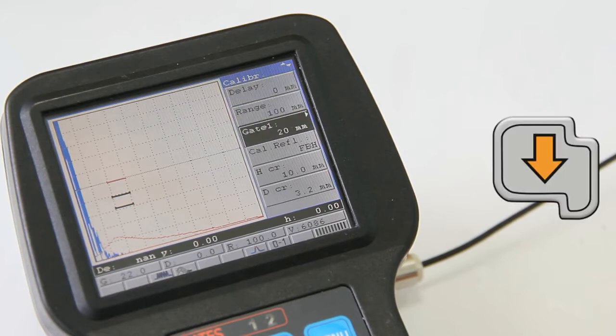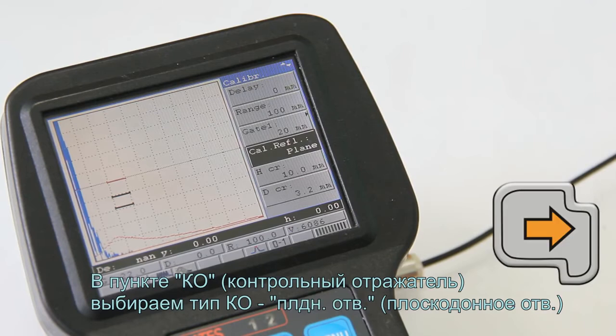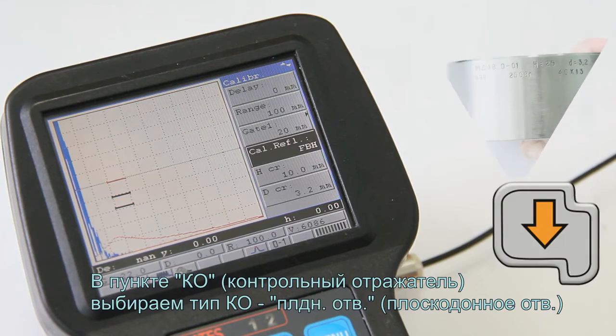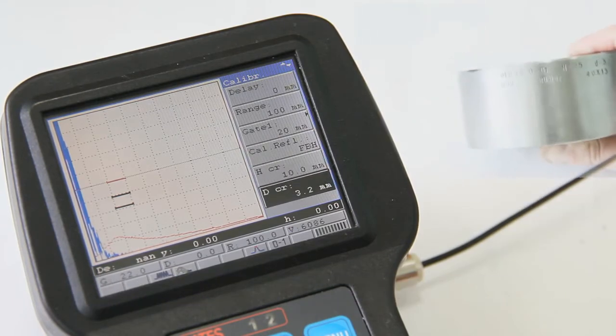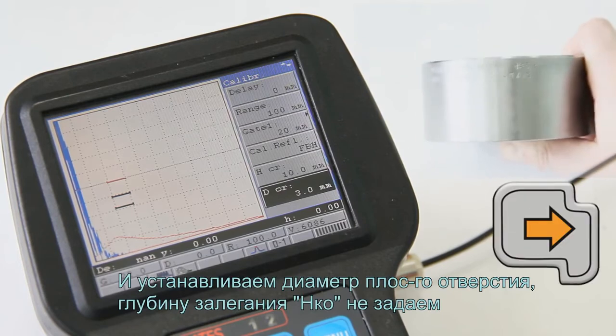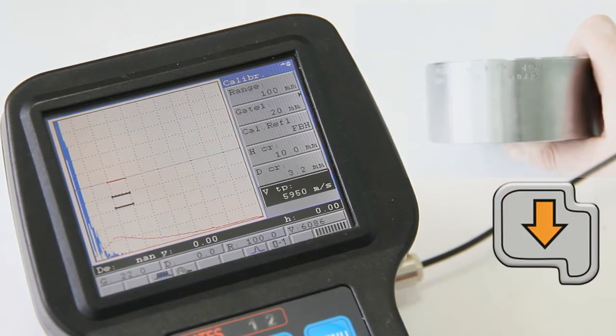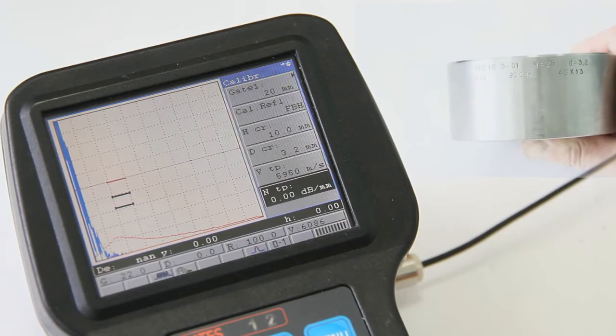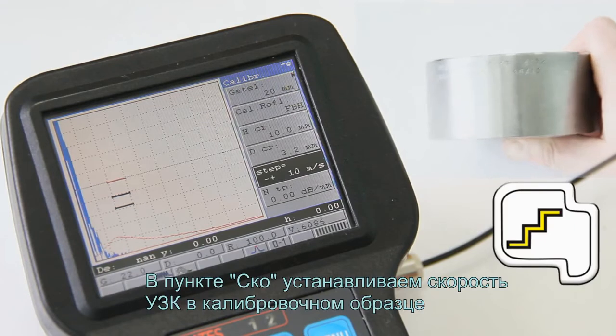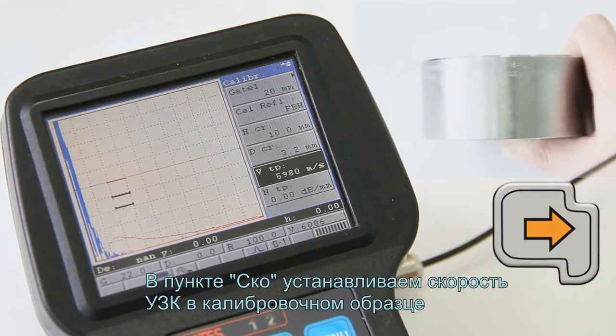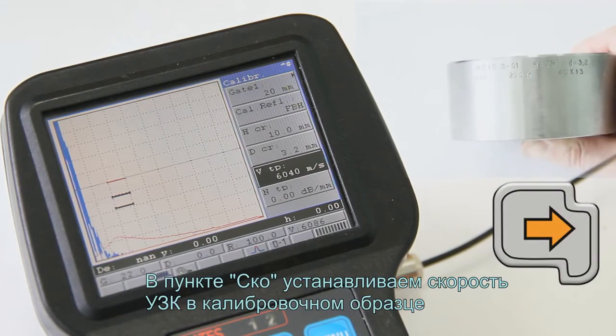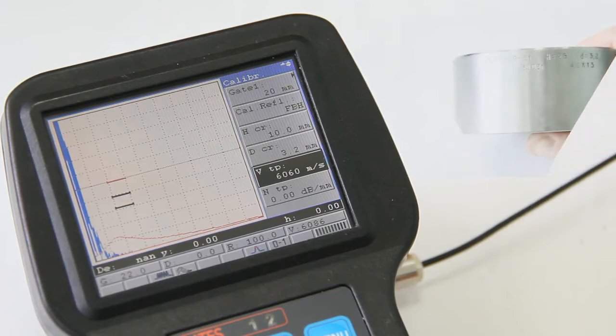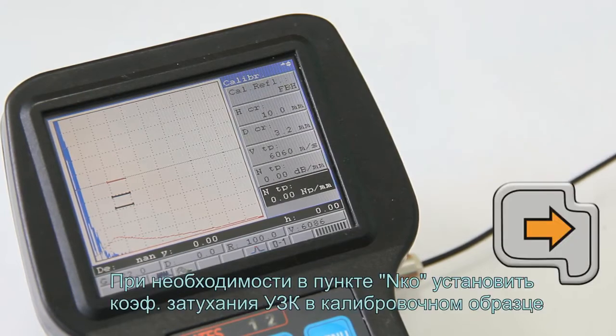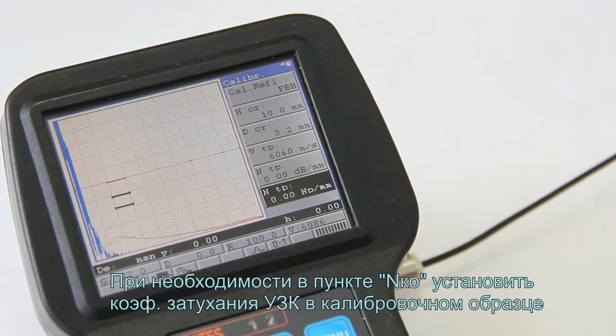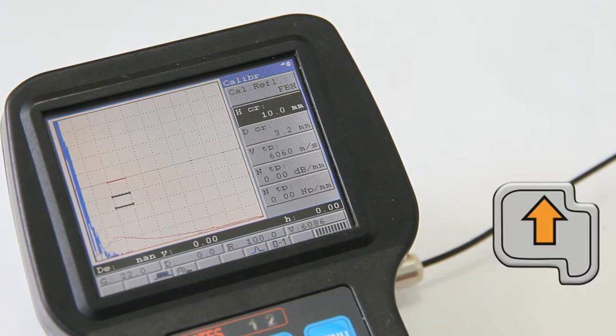In calibration reflector item, select the type of calibration reflector, FBH, flat bottom hole, and set the diameter of calibration reflector DCR, and do not set the depth of calibration reflector. In VTP item, set the sound velocity in the calibration block. If required, set up the coefficient of acoustic attenuation in the block and in NTP item.